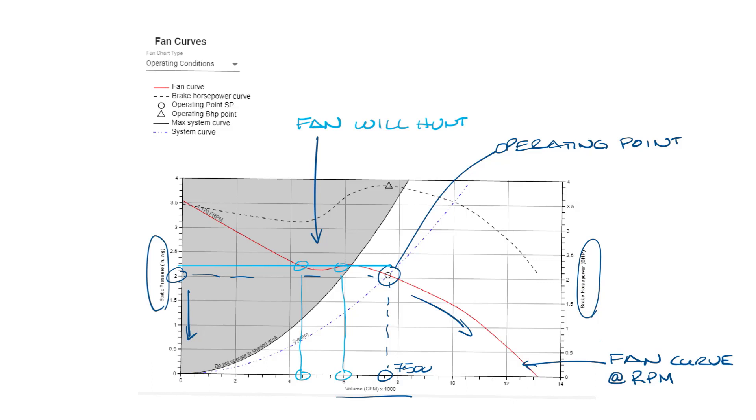And some fan curves won't have this dip. You'll see something that looks more like this, but what you need to know is you want to avoid operating in any area where the slope is positive.